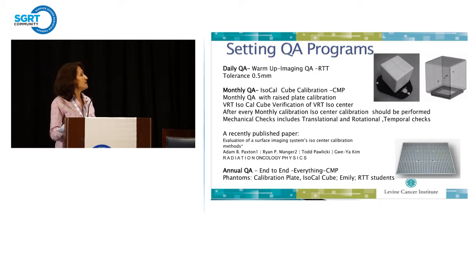treating your patients. For monthly QA, there is a plate calibration, the plate calibration monthly QA, and also there is an IsoCal calibration. They both do different things, and the IsoCal Cube basically fine-tunes the calibration that you do with your monthly QA. And that needs to be done after every monthly QA check.